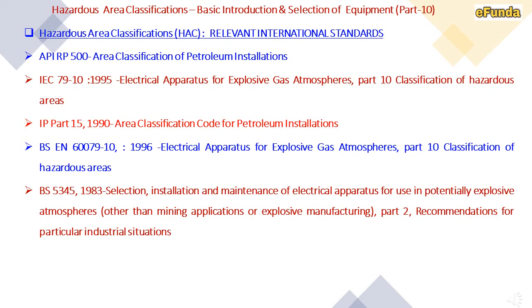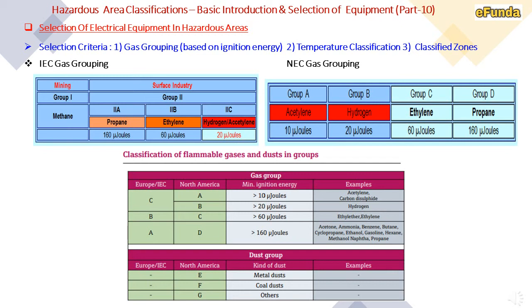Selection of electrical equipment in hazardous areas has three criteria: gas grouping based on ignition energy, temperature classification, and classified zone. IEC gas grouping: mining Group 1 is methane; surface industry Group 2A is propane at 160 microjoules; Group 2B is ethylene at 60 microjoules; Group 2C is hydrogen/acetylene at 20 microjoules. NEC gas grouping: Group A is acetylene at 10 microjoules; Group B is hydrogen at 20 microjoules; Group C is ethylene at 60 microjoules; Group D is propane at 160 microjoules.